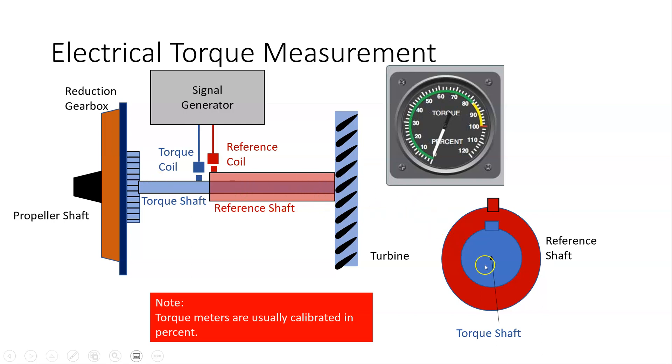So here we are looking in, so this is the torque shaft inside the reference shaft. What's going to happen is when the shafts turn, every time the magnet passes the pickup coil it will generate a signal. And the signal generator here will look at that signal, do some analysis on it, and then output the torque as a percentage.